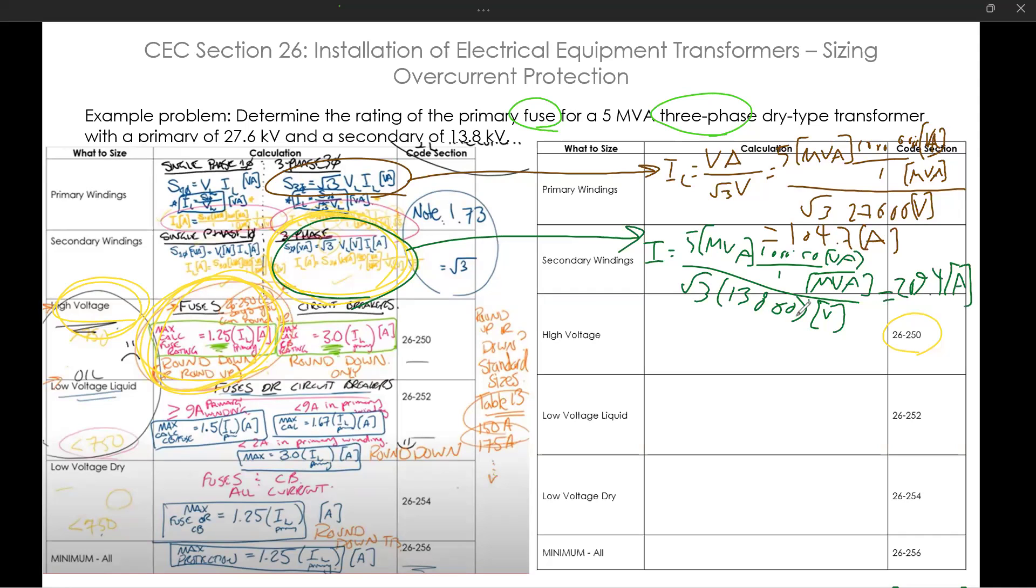But this question is just asking to determine the rating of the primary fuse. So I'm using a fuse, which fuses actually have this section, subsection two. Subsection two actually says that you can round up, but normally we would round down. We'll talk about that once we calculate it. So for fuse, we use this equation.